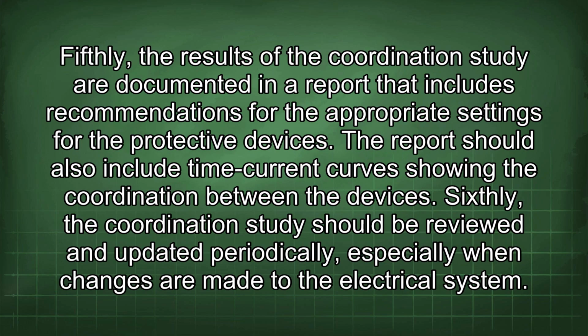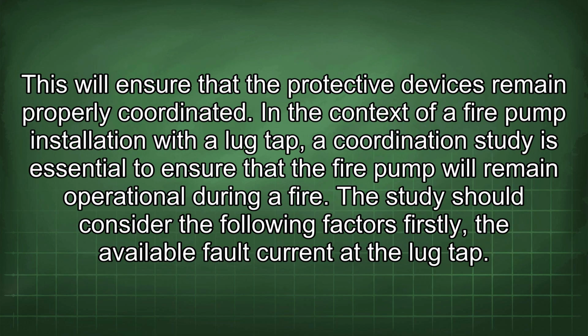Fifthly, the results of the coordination study are documented in a report that includes recommendations for the appropriate settings for the protective devices. The report should also include time current curves showing the coordination between the devices. Sixthly, the coordination study should be reviewed and updated periodically, especially when changes are made to the electrical system. This will ensure that the protective devices remain properly coordinated.